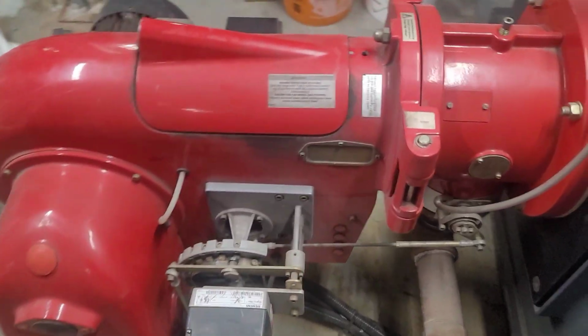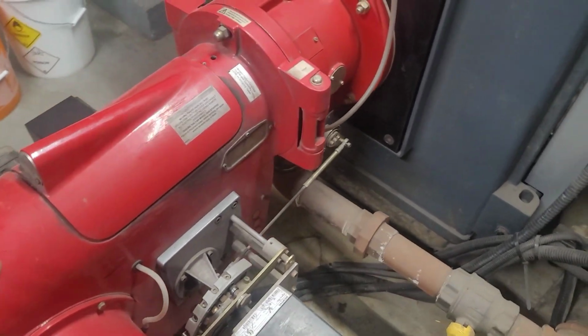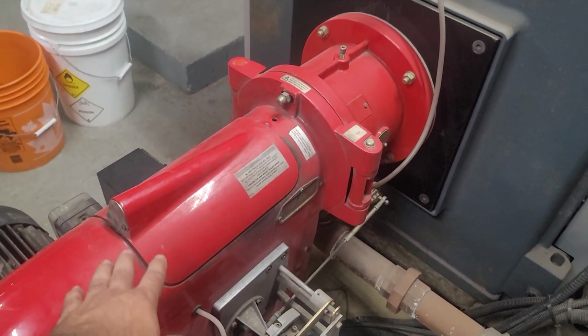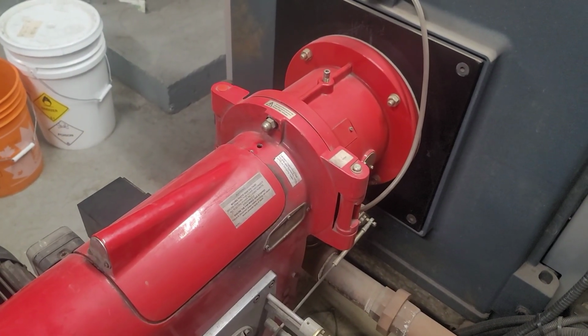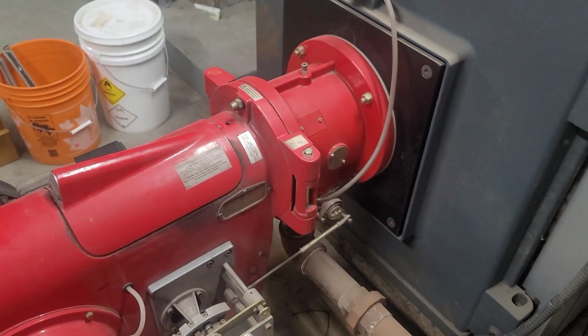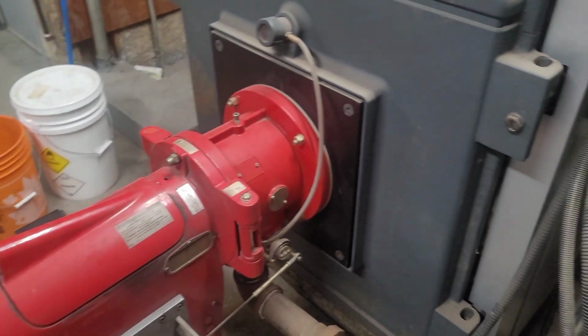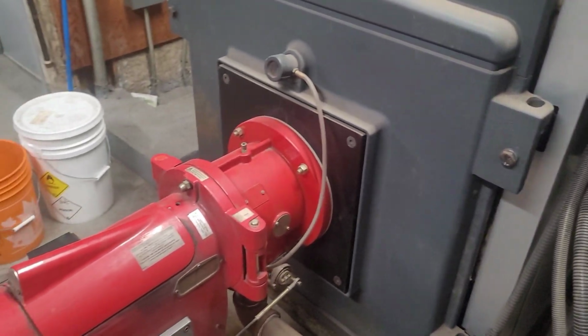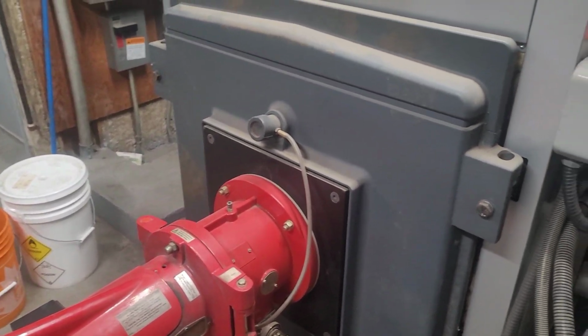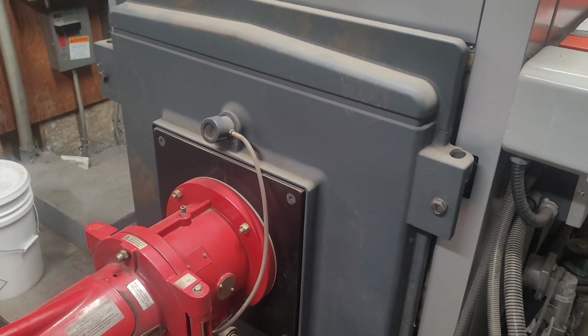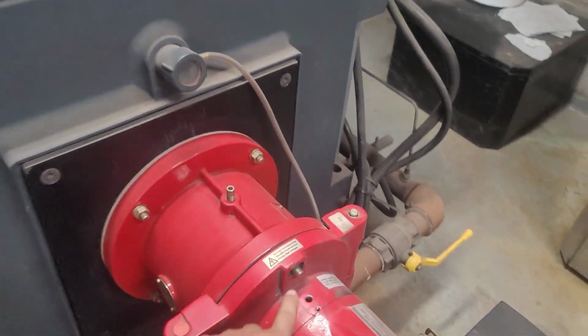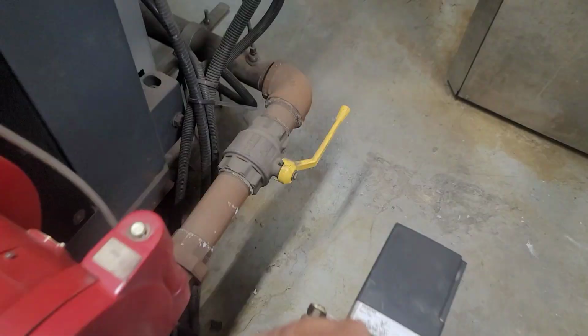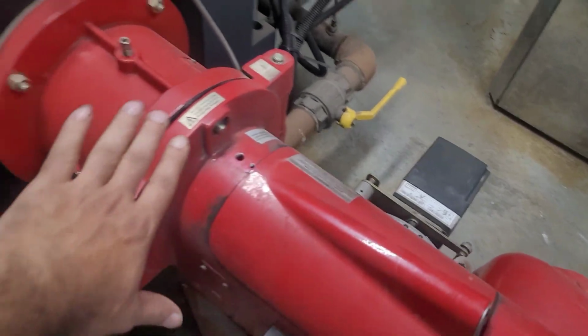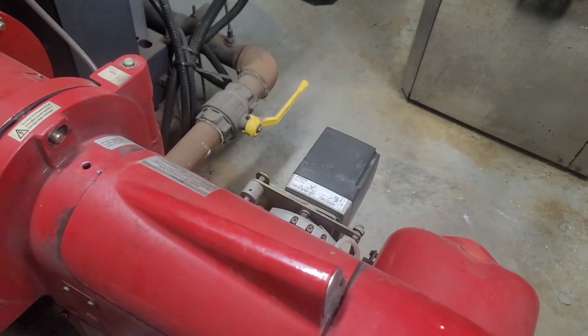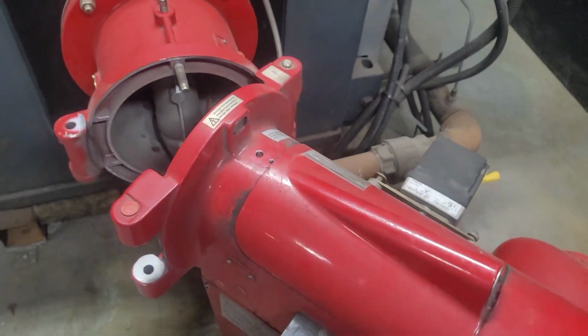And so let's open up the burner, and we'll replace the burner plate, igniter, and the flame rod. Once we are done, I'm gonna give it a try. We will test fire it and see how it's going. Okay, so I have taken out this nut, a linkage right there, and now there is a hinge, so it will open up like this, like so.